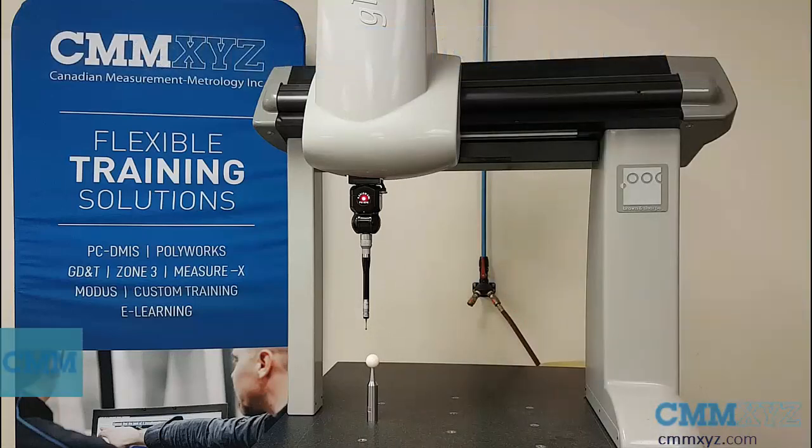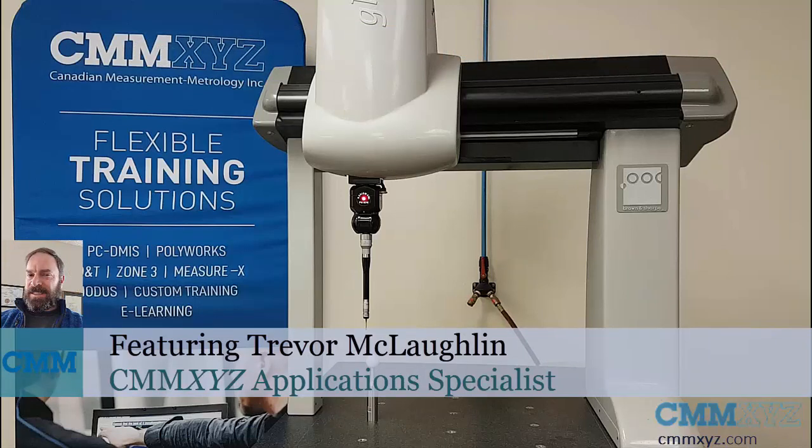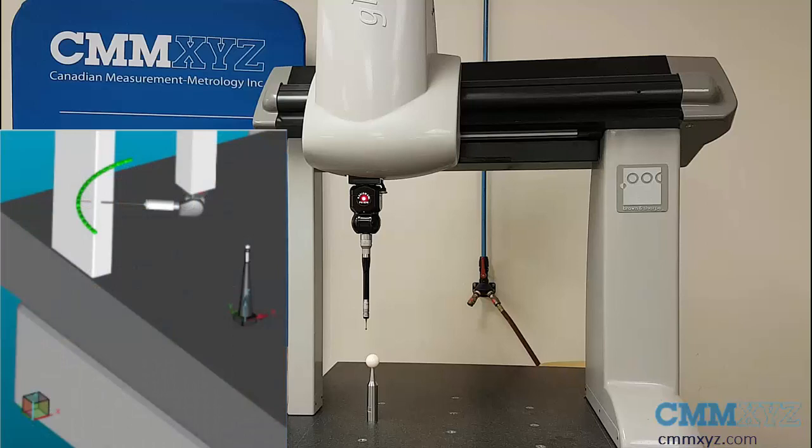Hey, so in this video I wanted to show you a great new feature that was introduced in PC-DMIS 2019 R1. This is the probe calibration collision check. This check was introduced to avoid crashing the probe when it swings around on a long build like this and could potentially smash into that bridge.